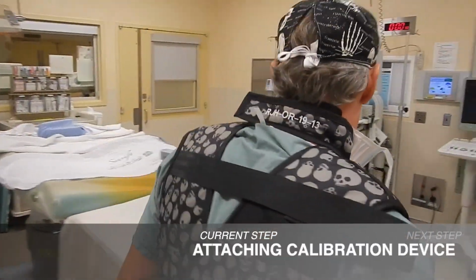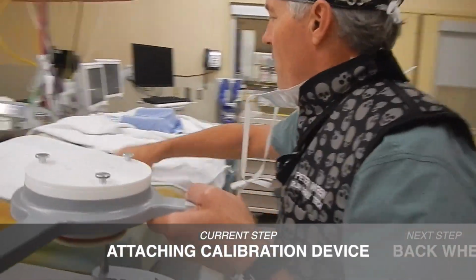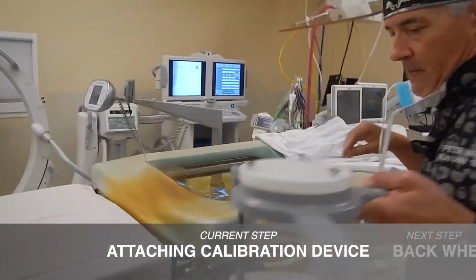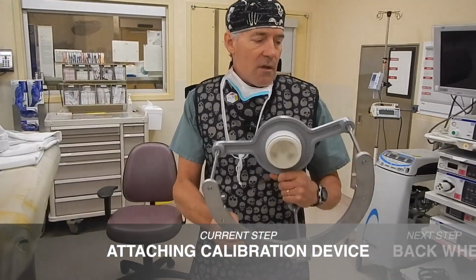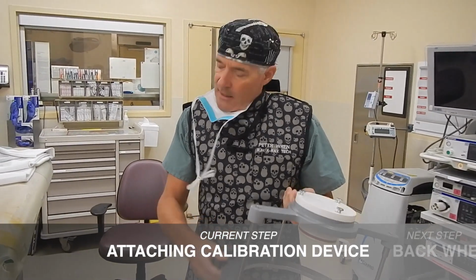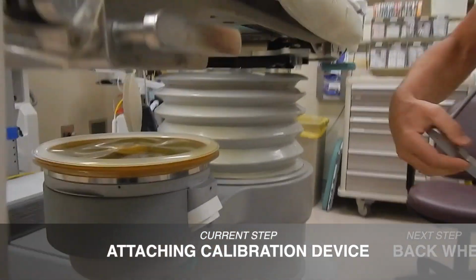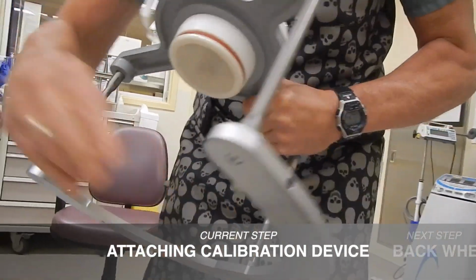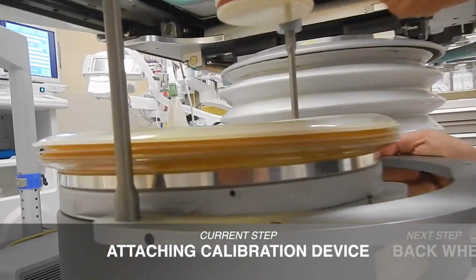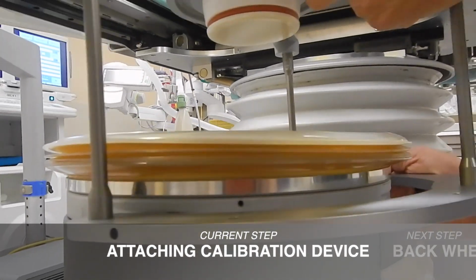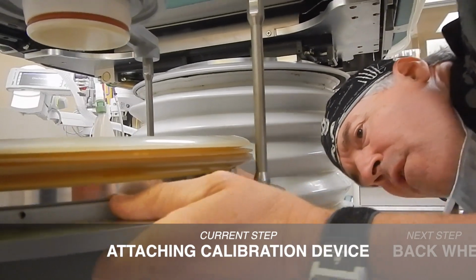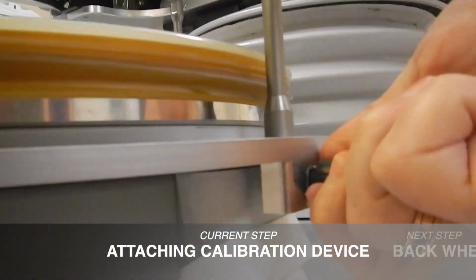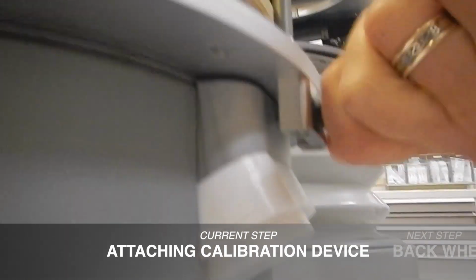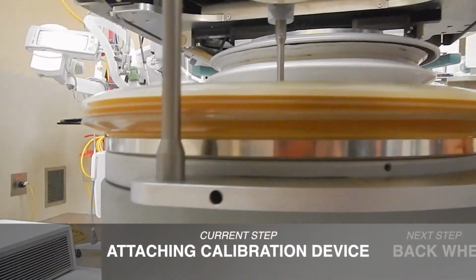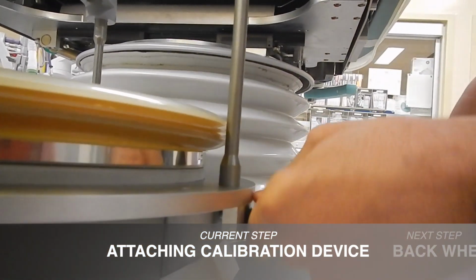And the reason for that is we're about to attach this. So this is the Phantom that is very critical in calibration, and it attaches to the therapy head. It has two knobs and a bolt. You line up the knobs with the grooves on the side of the therapy head, and the bolt with the little hole, and screw it in. Then give it a little wiggle to make sure it's tight.